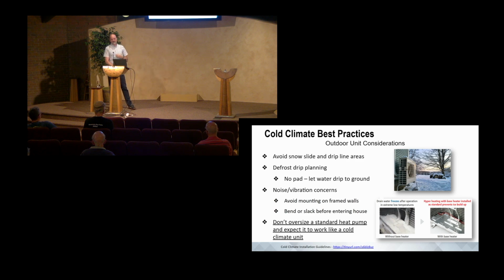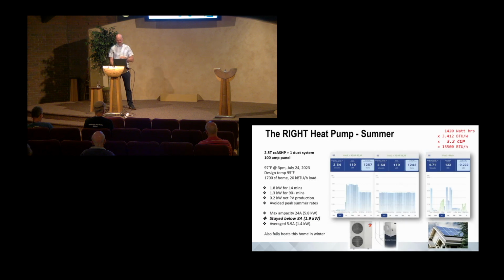Interesting question. The short answer is, on this big one right here, something like that size, you could get, I want to say, up to about 3 gallons for a very heavy, very wet, very snowy day. So we're talking upwards of an inch of really thick snow caking on that coil, and then going through defrost you could pick up upwards of 3 gallons.